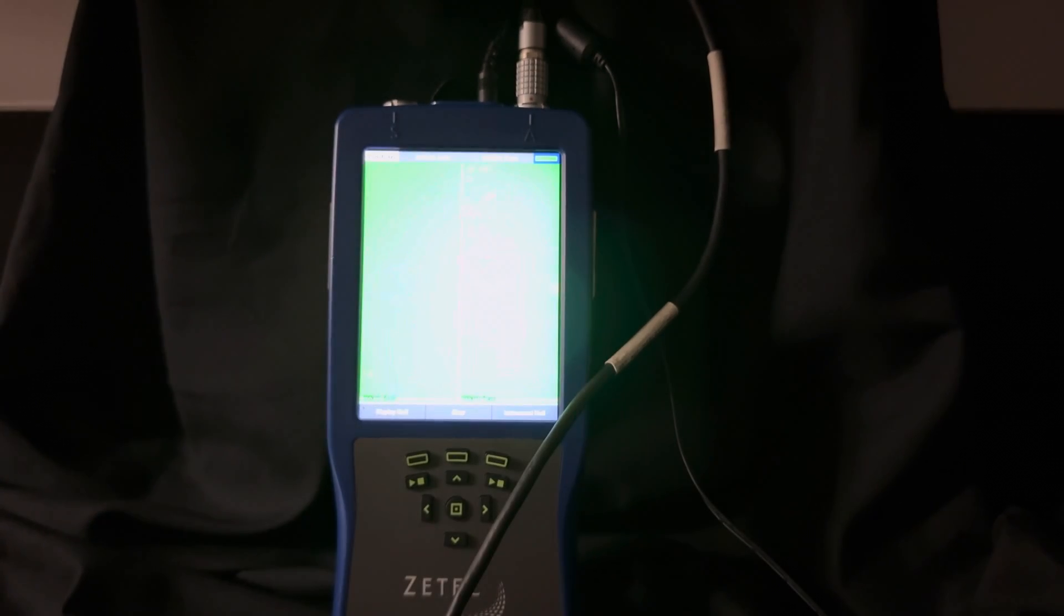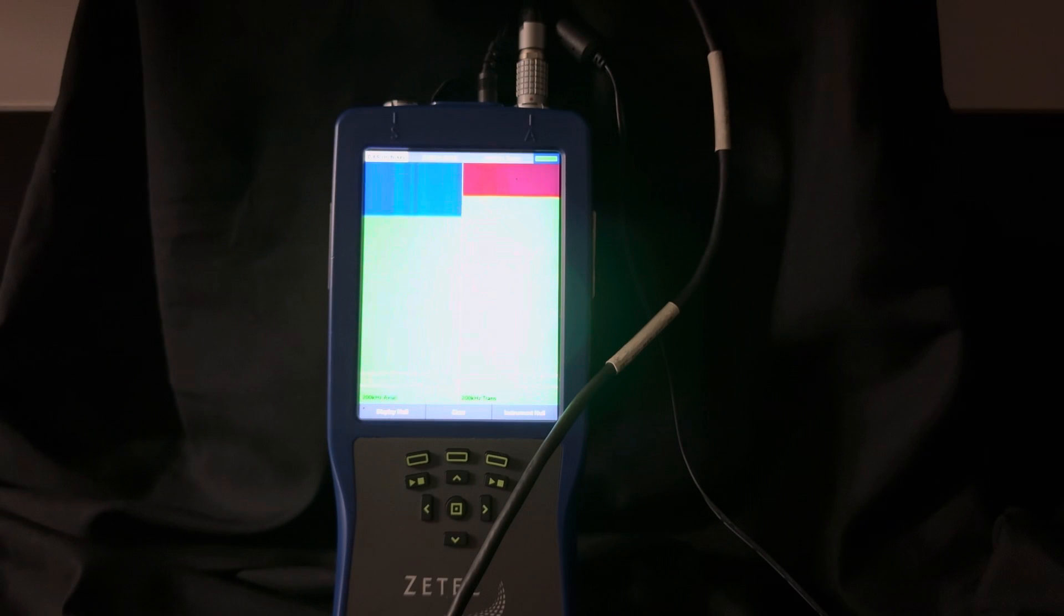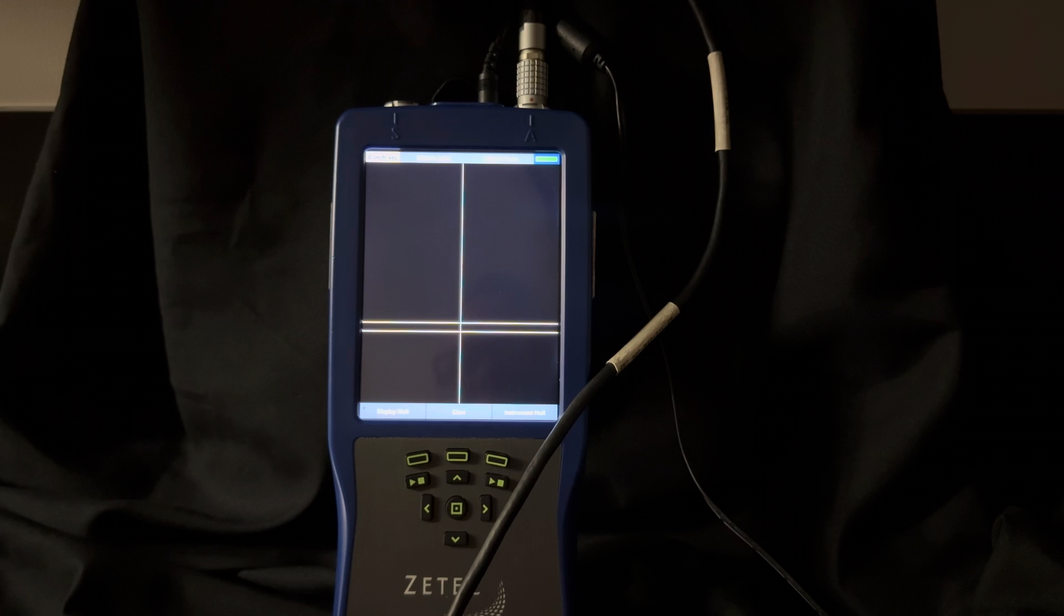I'm going to take and just place the array probe down in the good material next to my fastener and we hit instrument null just to make sure we're nice and sensitive.